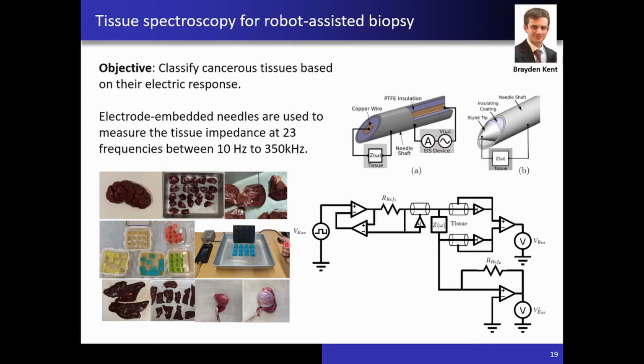This needle is connected to this spectroscopy circuit. So the needle here is the tissue. We have one of the electrodes here, one of the electrodes there. This is a very simple arrangement that was custom made by a company for us. This system delivers a current from the primary to the secondary electrode, and we also measure the voltage difference that creates. So this part here is simply a current source, and this second part here is a differential voltage measurement system. We can do this at 23 frequencies that range from 10 Hz to 350 kHz.